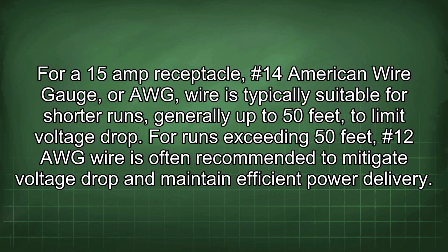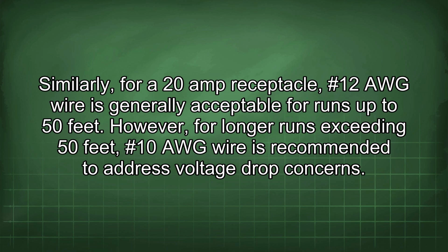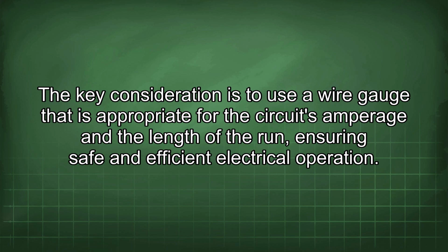For runs exceeding 50 feet, #12 AWG wire is often recommended to mitigate voltage drop and maintain efficient power delivery. Similarly, for a 20 amp receptacle, #12 AWG wire is generally acceptable for runs up to 50 feet. However, for longer runs exceeding 50 feet, #10 AWG wire is recommended to address voltage drop concerns. The key consideration is to use a wire gauge that is appropriate for the circuit's amperage and the length of the run, ensuring safe and efficient electrical operation.